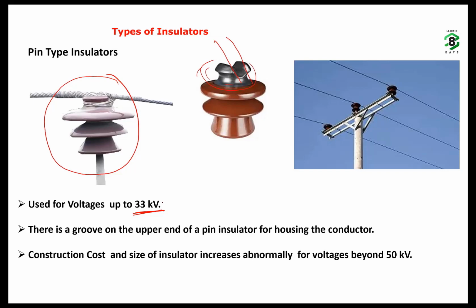There is a groove on the upper end of the pin insulator for housing the conductor. This is the groove where we house the conductor. Construction cost and size of the insulator increase abnormally for voltages beyond 50 kV. For voltages beyond 50 kV, constructing a single pin insulator is difficult, and even the cost will increase exponentially.